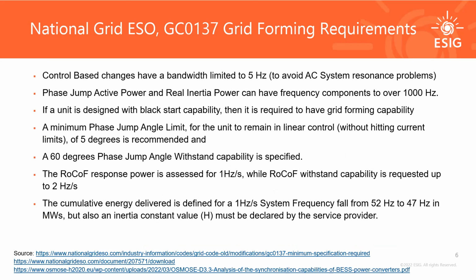Apart from these specifications that are for the grid, they also have some requirements for ride-through. So for example, there is a 60-degree phase jump angle withstand capability requirement. And there is also a minimum phase jump angle limit, which prescribes the phase jump angle for which the inverter shouldn't hit its equipment limit.